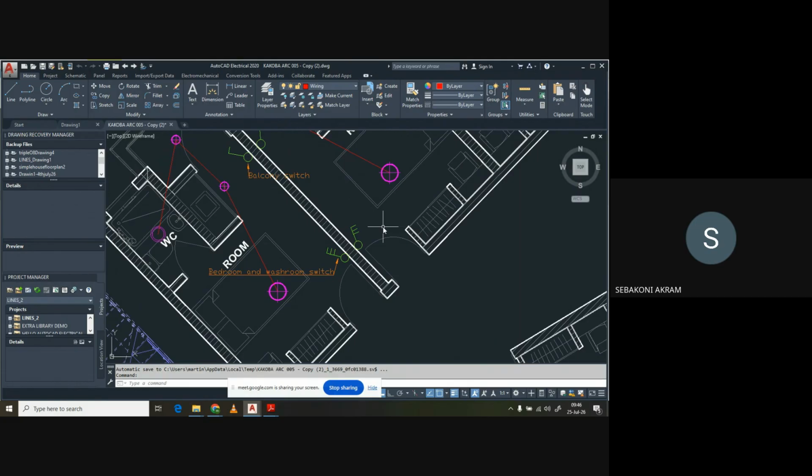You getting me? Why is it that what you've done, I'm seeing the connections between the lights? I'm seeing like you're drawing as if it could be a conduit, but really you don't have to show that. It's up to the technician how he's going to lay his conduits to those different points. Your point is you have to show the controls from the switch to the light.